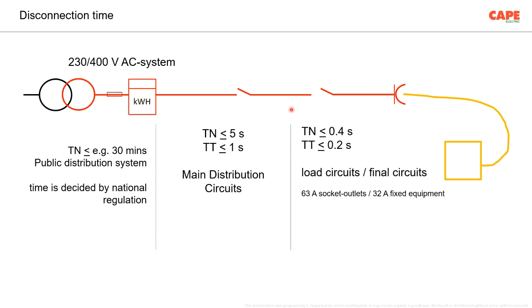In the fixed part of the electrical main distribution circuits, the disconnection time maximum allowed is, in case of TN system, 5 seconds, TT system 1 second. For the load circuits, the final circuits, 63 amp socket outlet devices or 32 amp fixed equipment, the disconnection time recommended in the standard, these are the maximum recommended times, please understand, in TN system 0.4 second, in TT system 0.2 second.